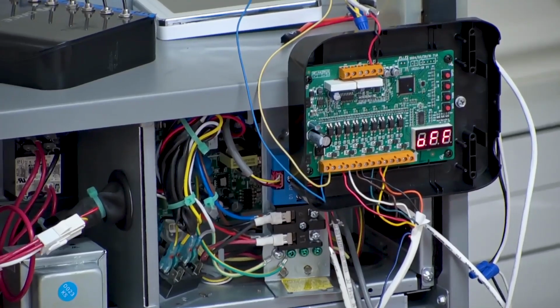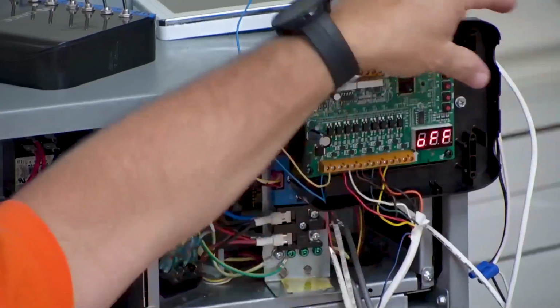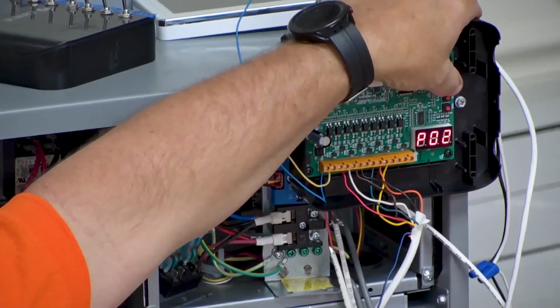01. 01 means at startup this would become the master. Let's say you don't set that. If you don't set it, then you're going to get an error code because you have no master indoor unit. You have to have a master indoor unit with a MultiPro system. So if that was the master, or if you want to change it to the master, you would set that P10 code. I'll go back to it just real quick here.